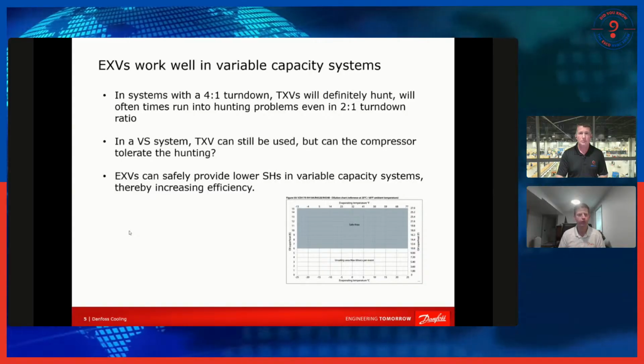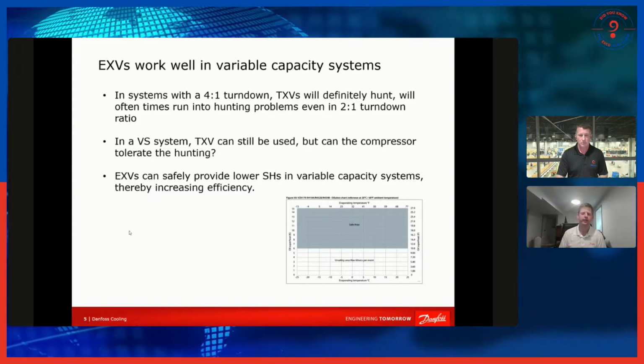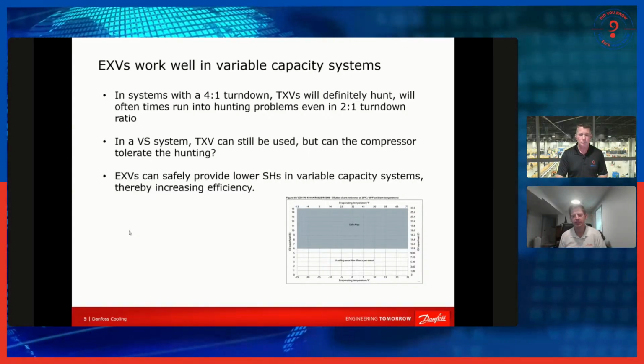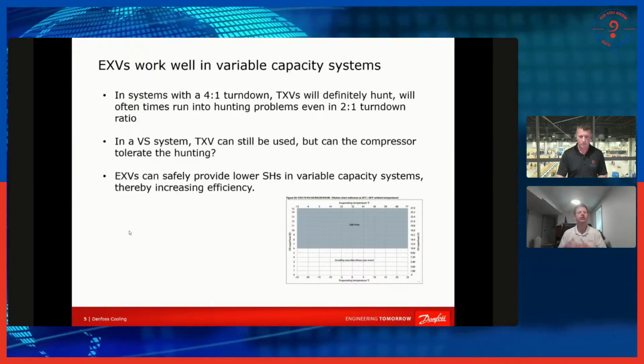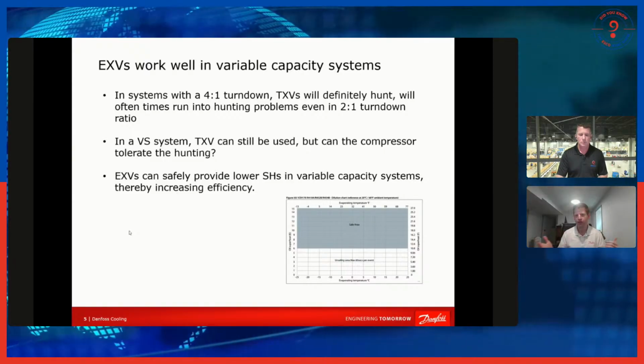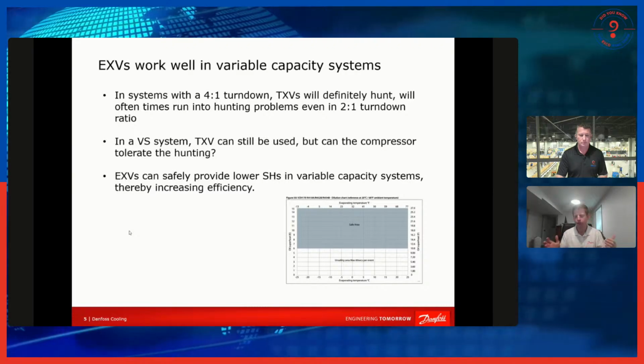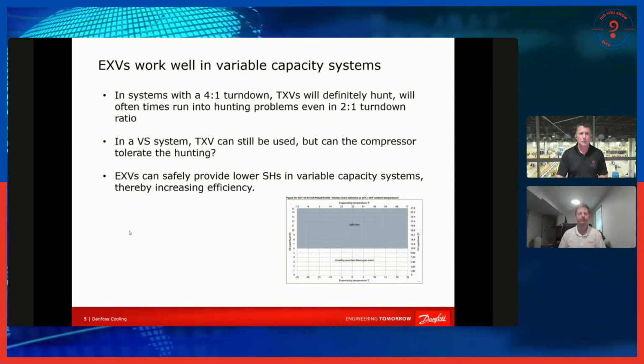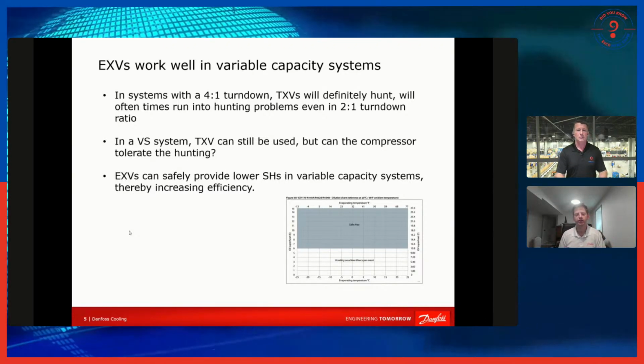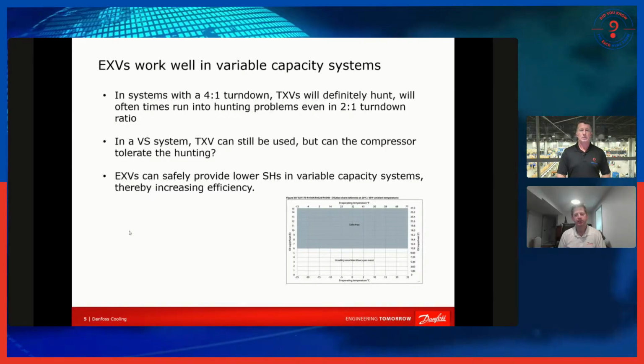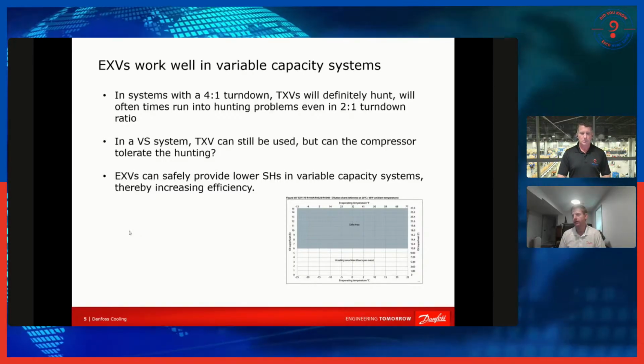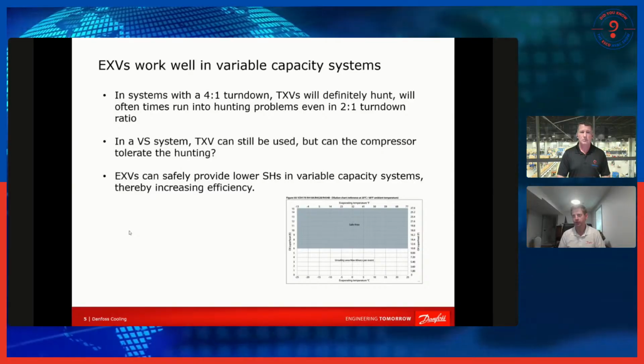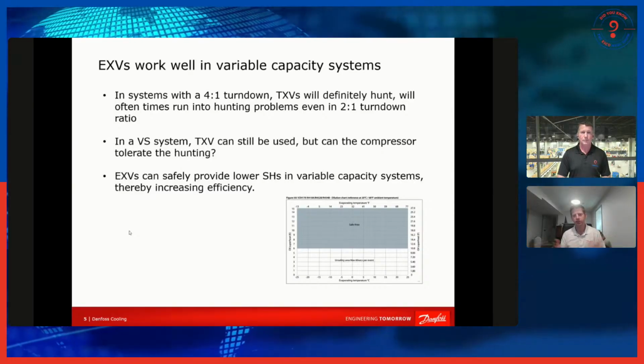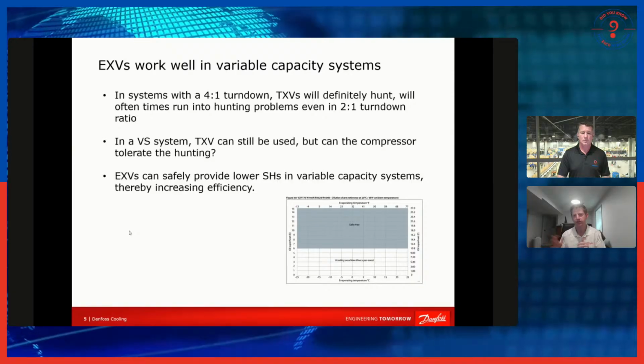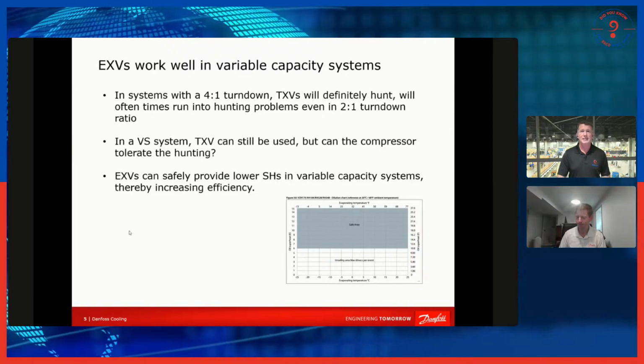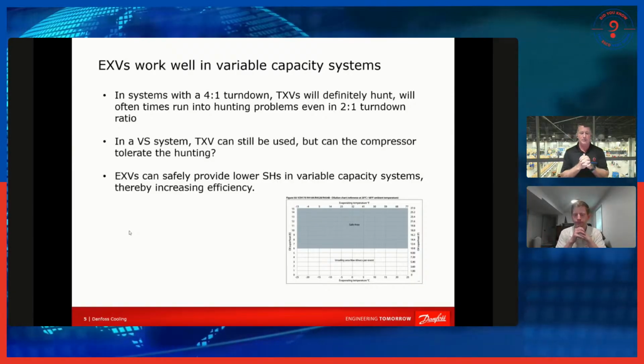And that's true whether you're working on a gigantic chiller. Someone in the chat mentioned working on some ETS 400s. Those are going to be used on 400-ton R134A circuits, maybe a different refrigerant, but one of those low pressure refrigerants. But that also applies to when you're using an EXV or a TXV in a residential system. You can get away sometimes with an oversized TXV, but the EXV is going to provide more efficiency if it's set up properly. I saw that transition myself when I was in refrigeration.